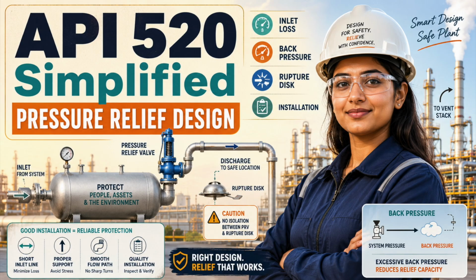Emergency relieving temperature matters. Discharge reaction forces matter too. High velocity flow creates momentum loads and bending moments that can be transmitted into the valve, piping, equipment nozzle, and structural supports. Discharge piping must be independently supported and correctly aligned. The pressure relief valve should never be used as a pipe support. Forced alignment with flange bolts is not alignment, it is stored stress.